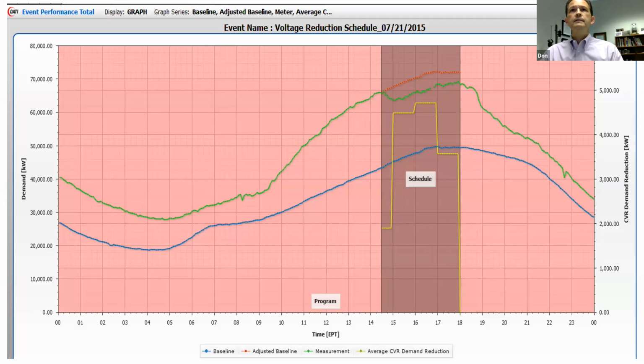We have a SCADA system constantly monitoring our load, AMI devices monitoring real-time voltages, and SCADA also monitoring our voltage regulators. At a given program time, an application lowers the voltage regulators across our system until voltage at the end of the line sends alarms telling us we've gone far enough to stay within local regulatory ANSI standards.